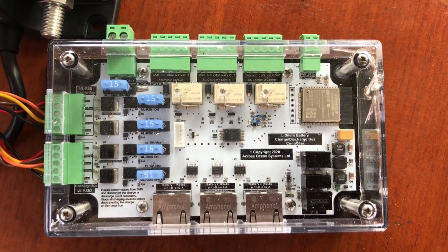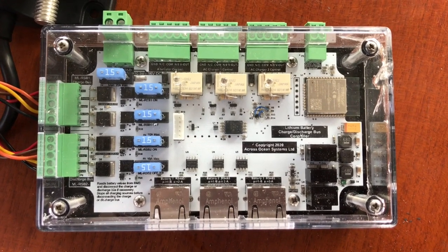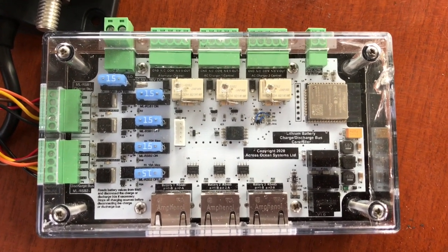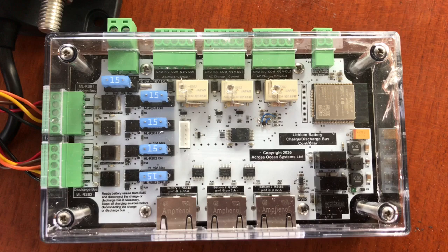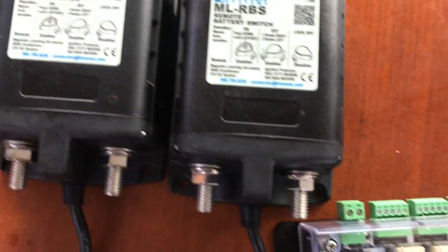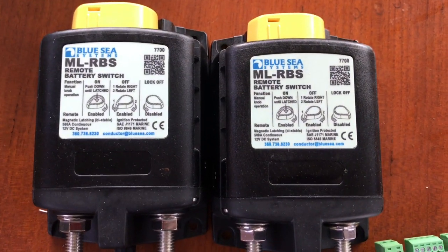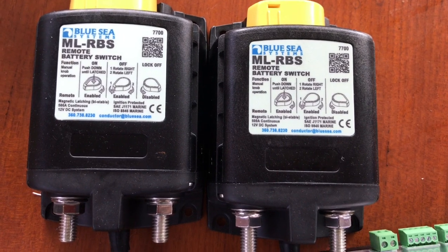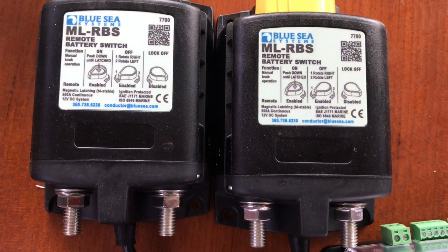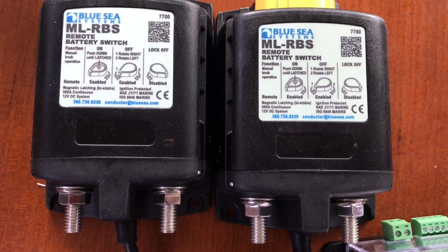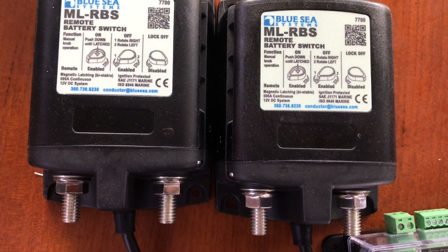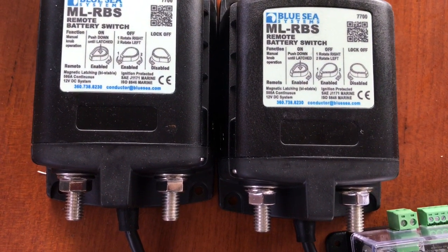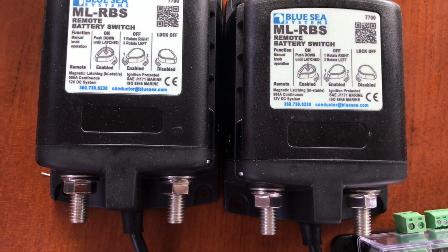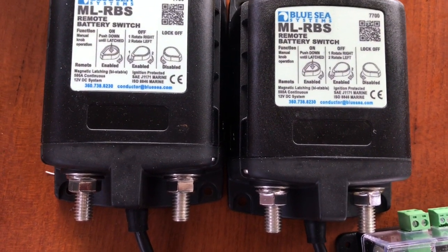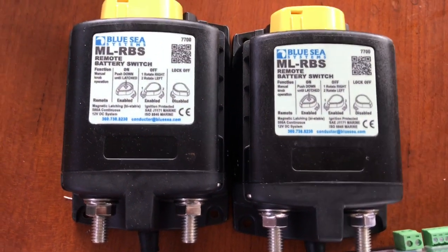So here is the battery management system that I just designed, and the software is not ready yet, but it will control the charge and discharge bus with those ML-RBS 500 amp relays, and they're bistable. As I said, they require just a pulse of 12 volts, about 5-6 amps for a momentary, and they will switch from one position to another.